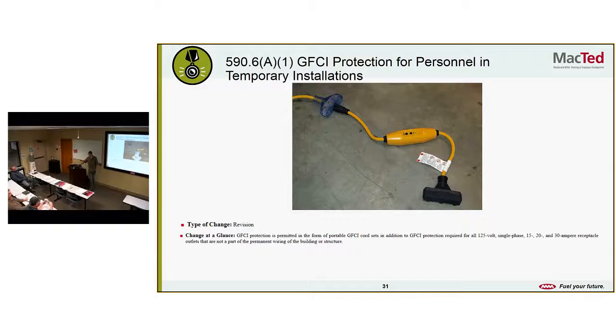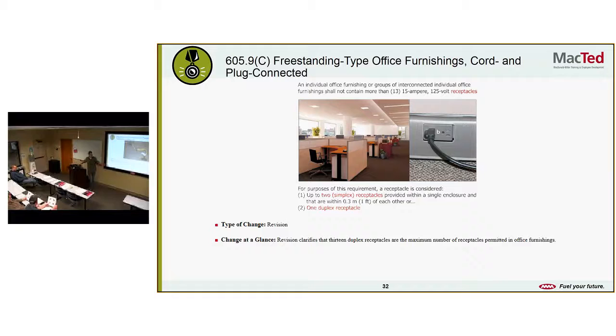GFI protection for personnel and temporary installations. GFI protection is permitted in the form of portable GFI cord sets in addition to GFI protection required for all 125 volt single phase 15 and 20 amp and 30 amp receptacle outlets that are not part of the permanent wiring of the building or structure. I'm not sure what the change was there. There's nothing highlighted. They're just saying you can use portables, is what it is. You can use those portable ones that we've had for years. So it was a clarification so that contractors don't have to install fixed GFI protection outlets. You can use the cord style.